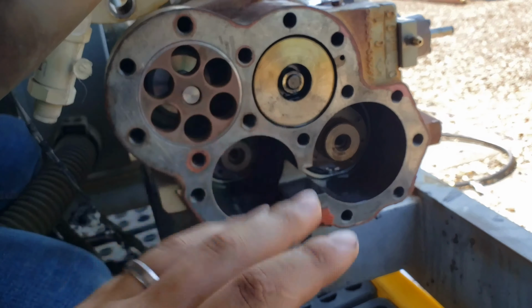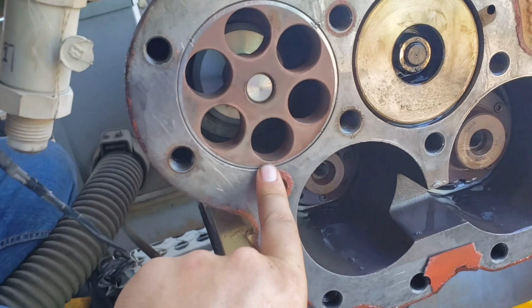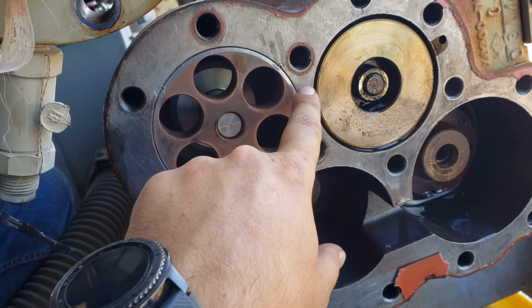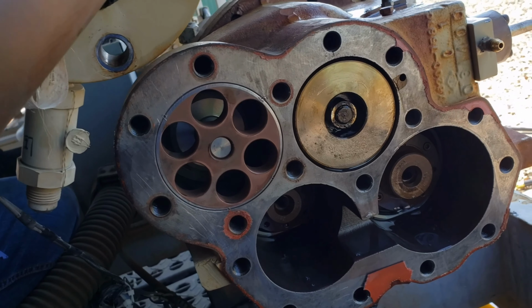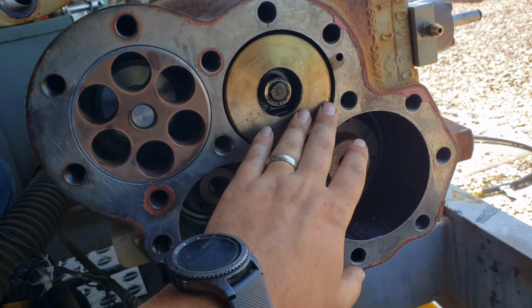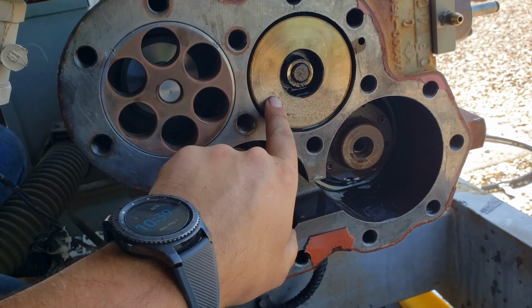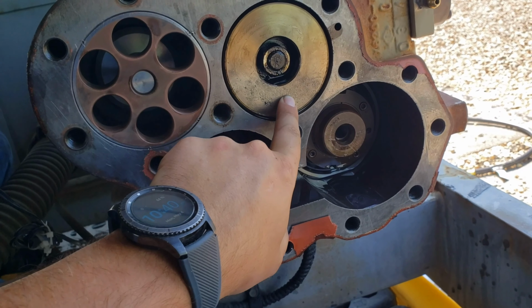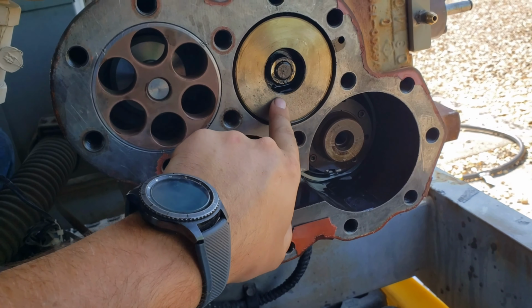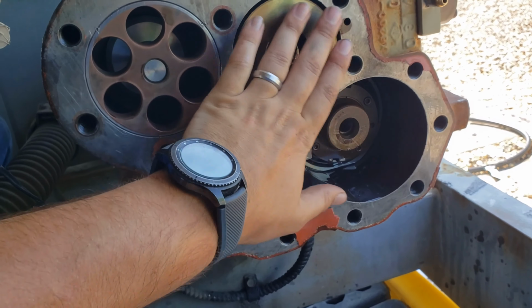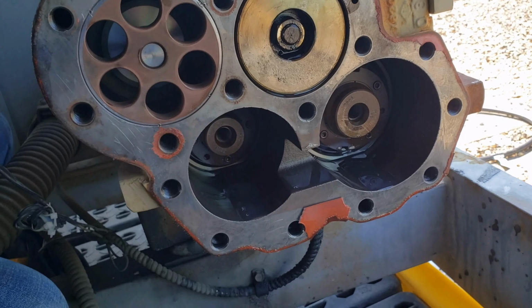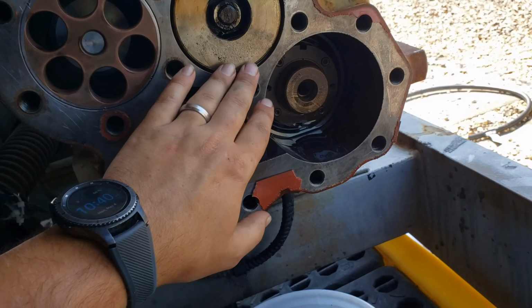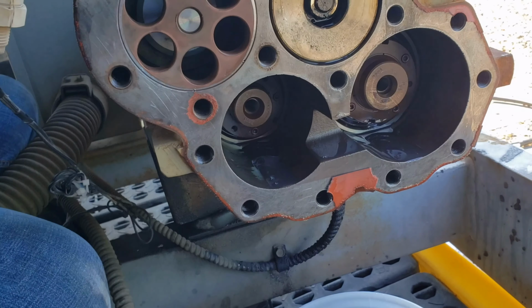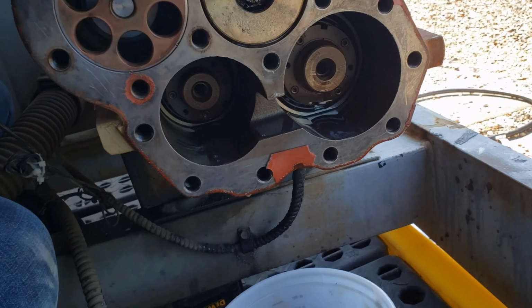Getting all this cleaned up, getting it back together. You can see right there, there's a bunch of service marks where people have definitely worked on this before. This compressor's had a lot of service done. I see a lot of pitting here on this slide valve, but it moves very, very smoothly. It's not sticking on us, so I'm not too worried about it. It wasn't having issues loading or unloading prior to this.